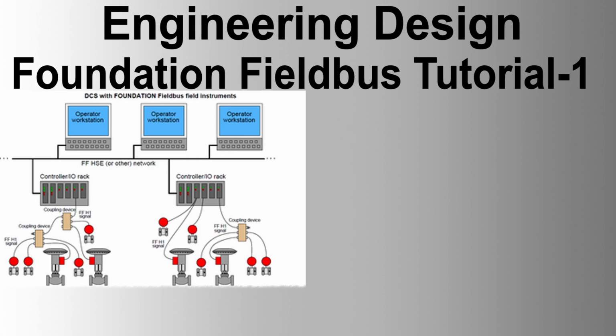Link Active Scheduler, LAS, has the role of controlling the medium access. The right to send a PDU is called a token. The LAS possesses the token and gives it to another device to allow it to send messages. The token is then returned to the LAS for further medium access control. Data link layer provides 3 levels of priority: urgent, normal, and time available, in this order. An urgent message is transmitted immediately even when other messages of normal or time available priority are in the waiting queue, and vice versa.